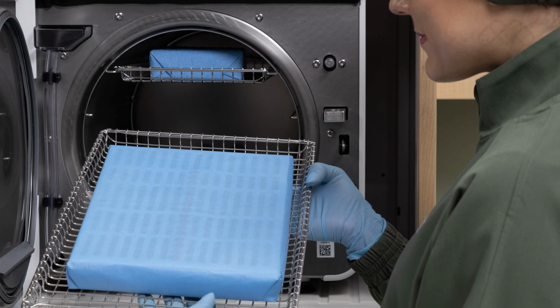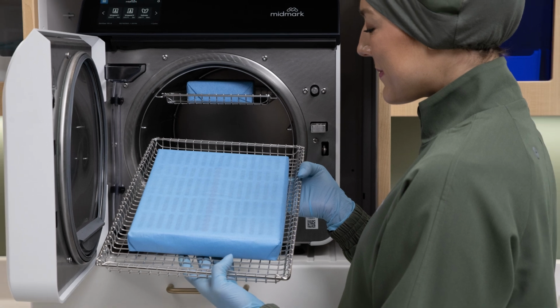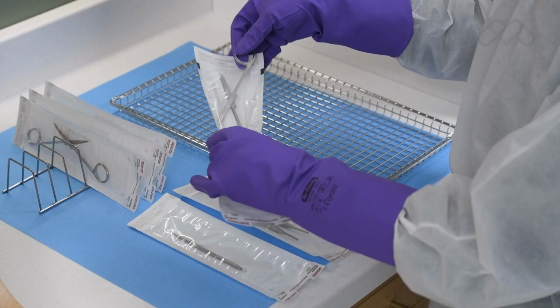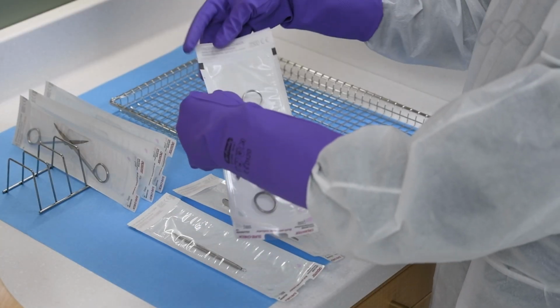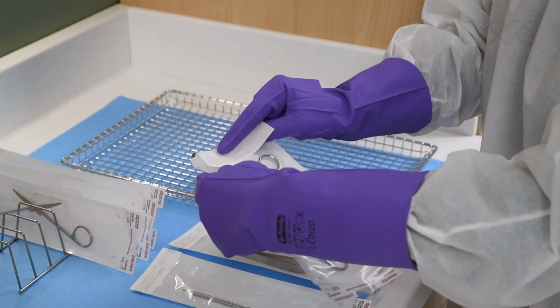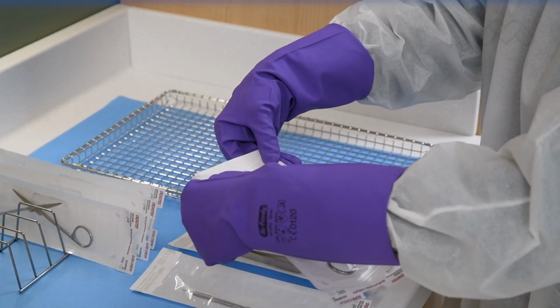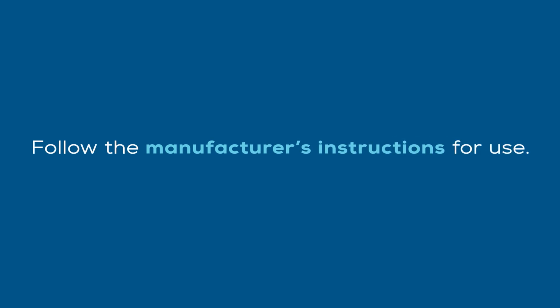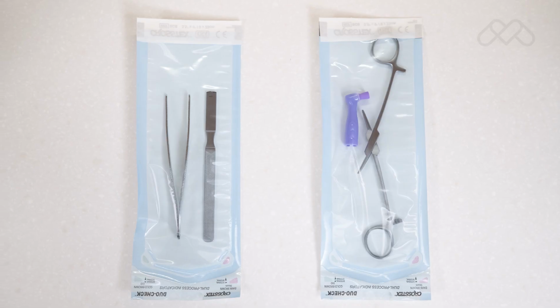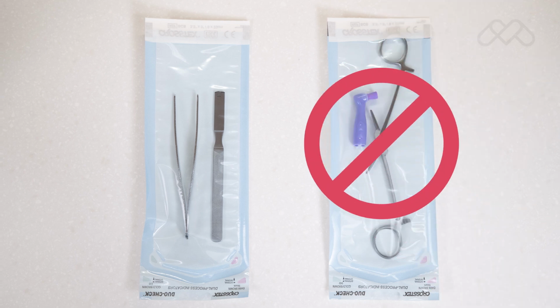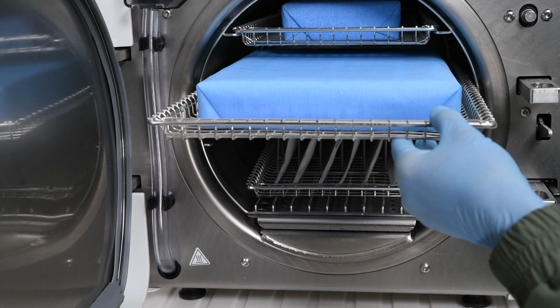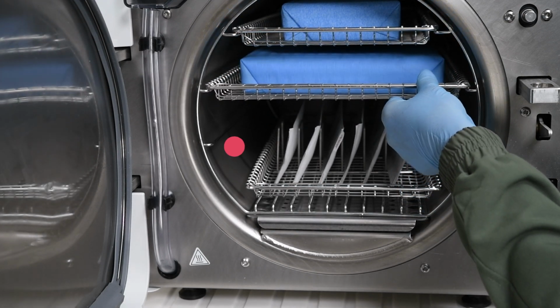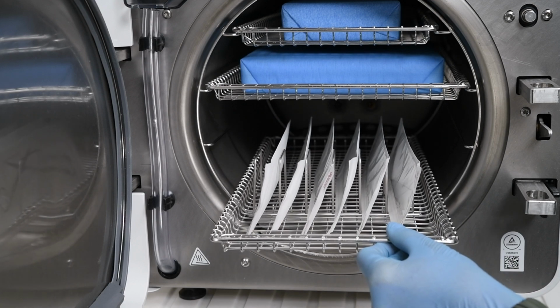The M9 and M11 are capable of sterilizing pouched or wrapped items to preserve sterility after processing. Use only sterilization pouches and wraps that have been cleared by the FDA and labeled for use with the steam sterilization cycle being used, and be sure to follow the pouch or wrap manufacturer's instructions for use. Instruments made from different materials should not be mixed in the same pouch or wrapped pack to avoid potential instrument damage. Pouches, wraps, and their included instruments should not touch the chamber wall. Clearance allows proper steam circulation and avoids potential instrument damage.